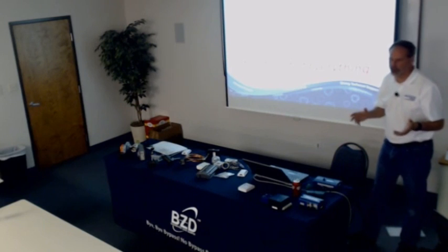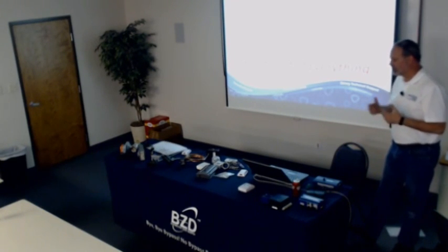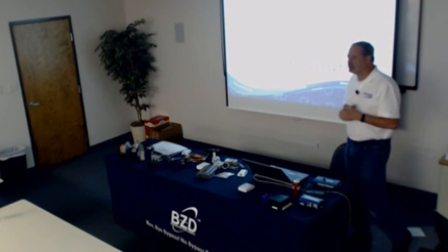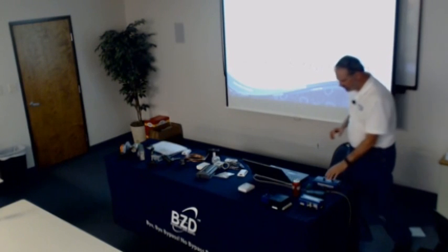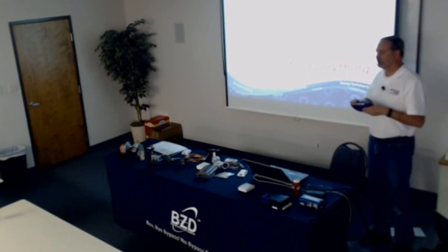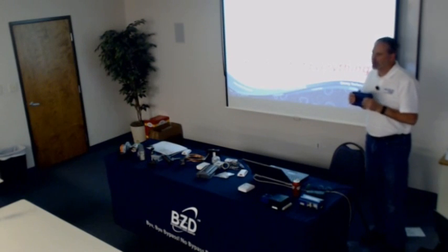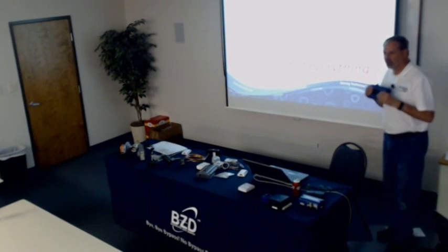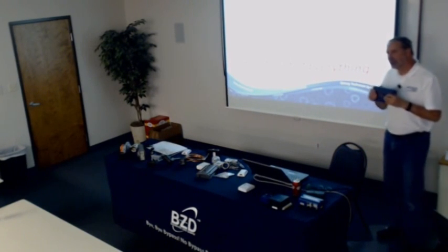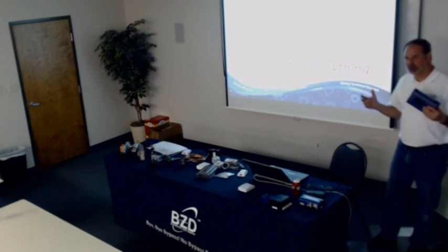But one of the things I wanted to close with was where is DDC Controls going? Where we see it going with both Distech and several other vendors is that it's going to be BACnet, but it's going to be over IP. We talked about maybe wireless wasn't the best solution, but what we're seeing is all of these controllers shortly, hopefully by almost all brands, are going to go on the same wireless network that my laptop's running on. It's the owner's IP network, and since it's BACnet over IP, it can run on the same infrastructure.